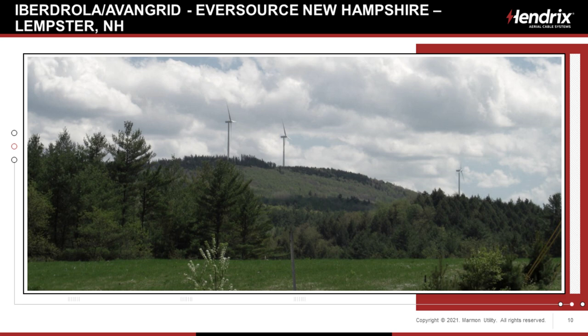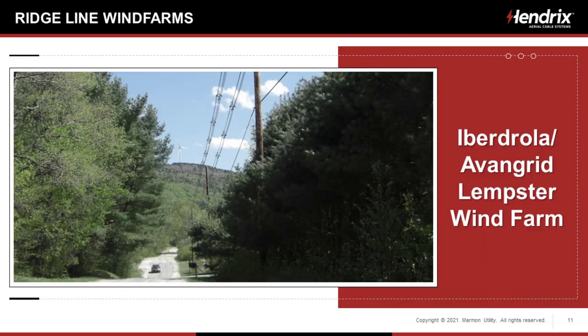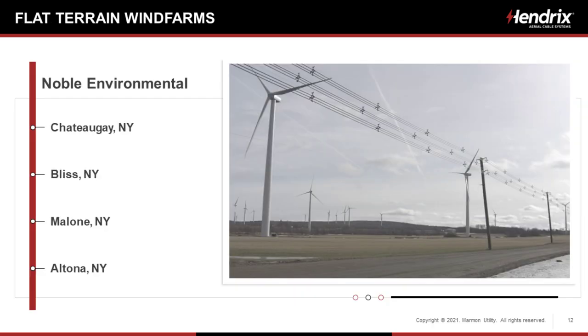Here's one of the many jobs we did with Iberdrola. Now it's called Avangrid Renewables. This is what we would call a ridgeline wind farm up in Lempster, New Hampshire. The turbines are suitably arranged along the ridges, and then we're bringing power down to the substation to get it back on the grid. And this is what that is going to look like. So, we just use the existing pole line going up to the mountain there, and we just put our collector circuits on it. So it's very compact, low profile, and non-invasive, not intrusive.